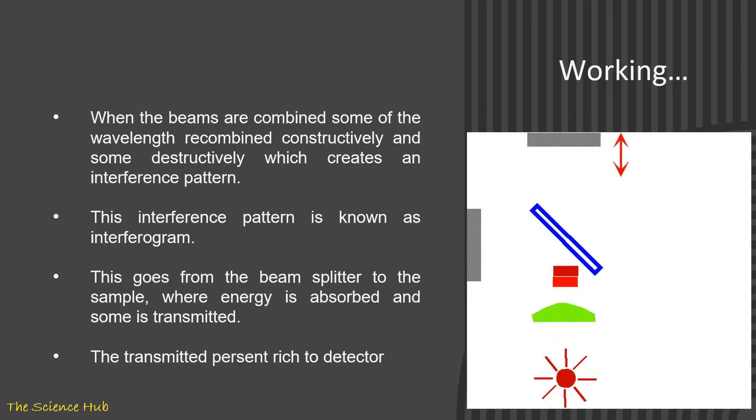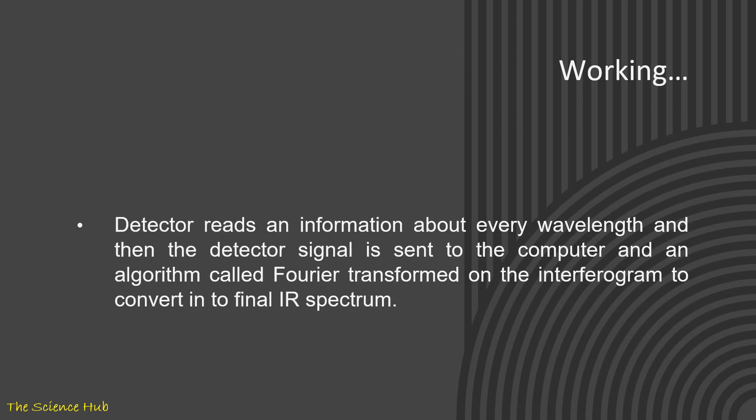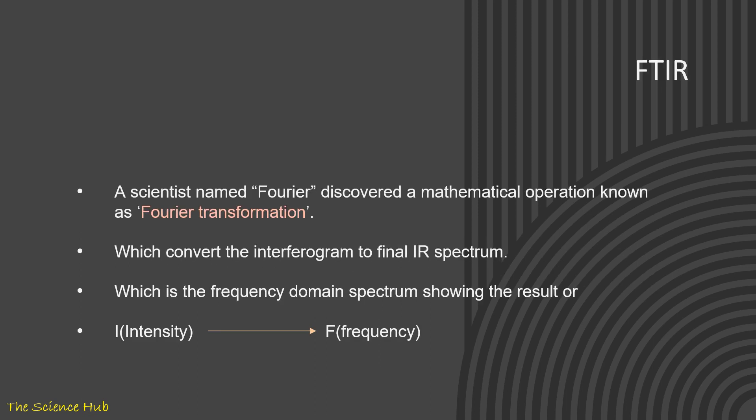When the beams are combined, some of the wavelengths recombine constructively and some destructively, which creates an interference pattern. This interference pattern is known as interferogram. This goes from the beam splitter to the sample, where energy is absorbed and some is transmitted. The transmitted percent reaches the detector. Detector detects information about every wavelength, and then the detector signal is sent to the computer, and an algorithm called Fourier transform on the interferogram converts it into the final IR spectrum. The scientist named Fourier discovered a mathematical operation known as Fourier transformation which converts the interferogram to final IR spectrum, which is frequency domain spectrum showing the result or intensity to frequency conversion.